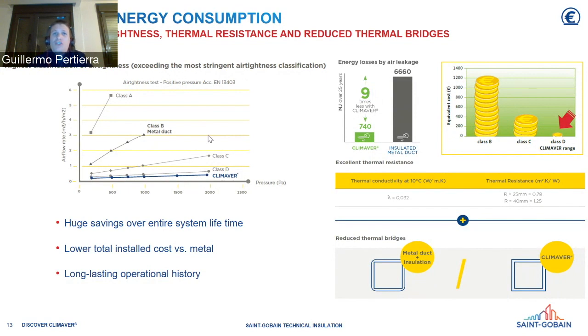Additionally, CLIMAVER has a very good thermal conductivity of 0.032. That means with 25 millimeters, we have a thermal resistance of 0.78, and with a thickness of 40mm, we have 1.25 of thermal resistance. So you can find a product in our range to achieve the thermal resistance you need for your project.